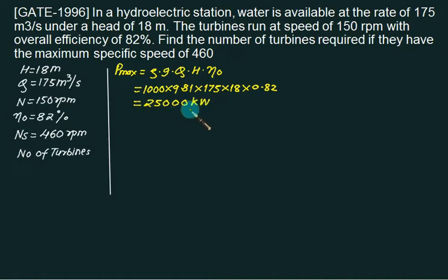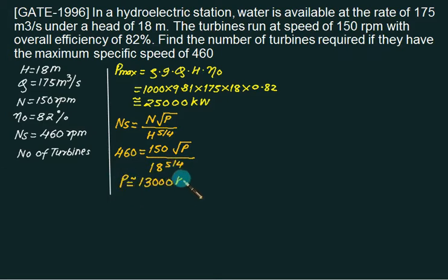Now using the specific speed formula, we can calculate the power developed for one turbine. So we have Ns equals N times square root of P divided by H to the power 5/4. Ns is given as 460, N equals 150, P we do not know, H equals 18 to the power 5/4. So power developed by one turbine will be 13,000 kilowatts.